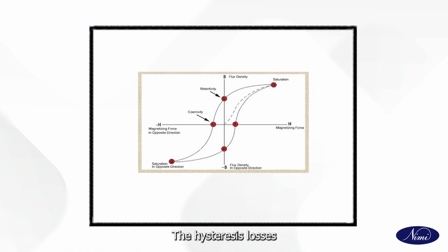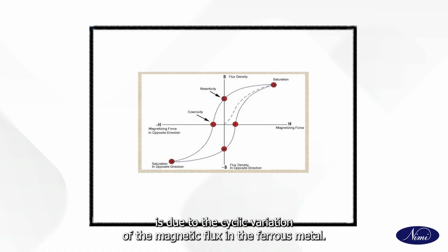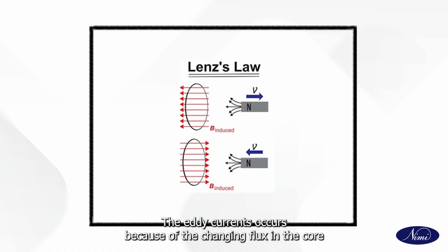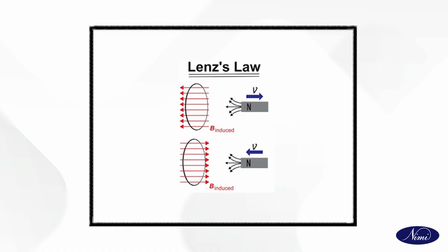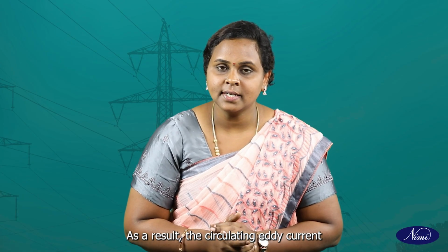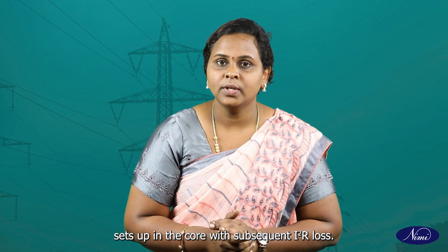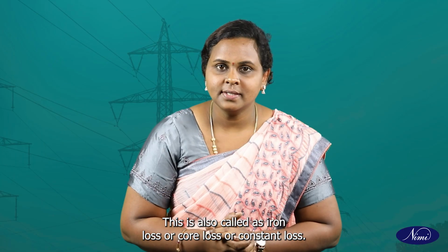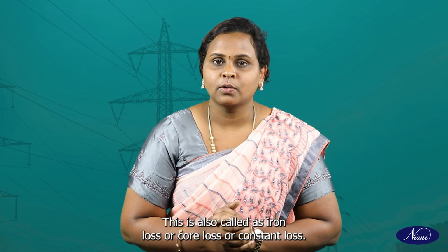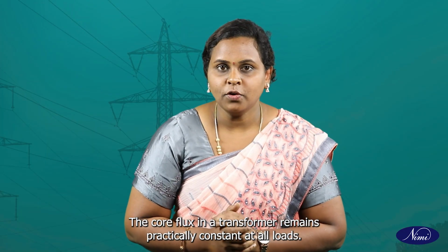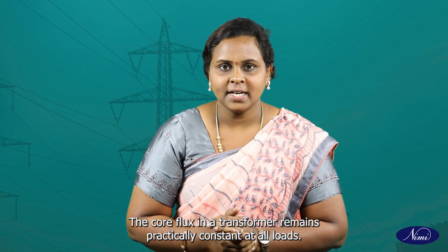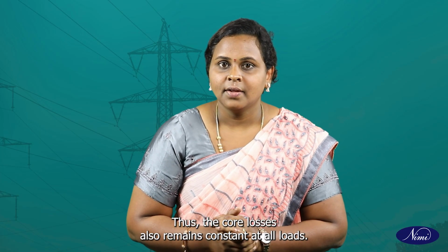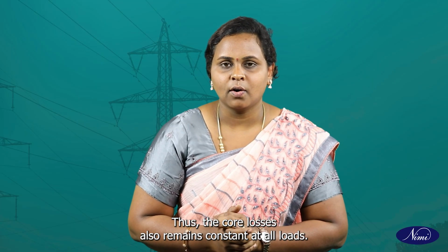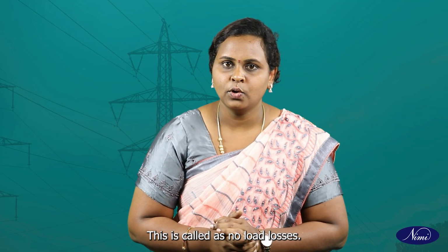The hysteresis loss is due to the cyclic variation of the magnetic flux in the ferrous metal. The eddy currents occur because of the changing flux in the core according to Lenz's law, inducing a voltage in the core. As a result, a circulating eddy current is set up in the core with subsequent I square R loss. This is also called iron loss, core loss or constant loss. The core flux in a transformer remains practically constant at all loads, thus the core losses also remain constant at all loads. This is called no load losses.